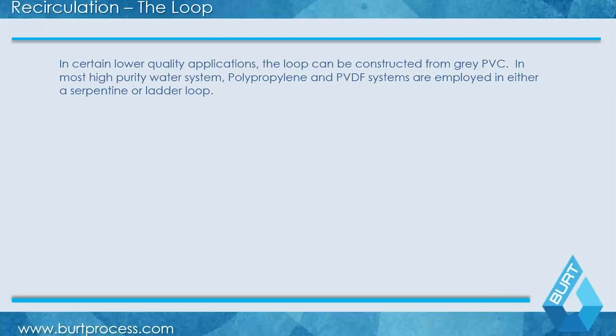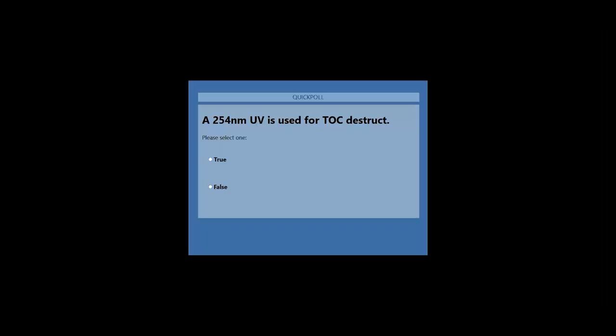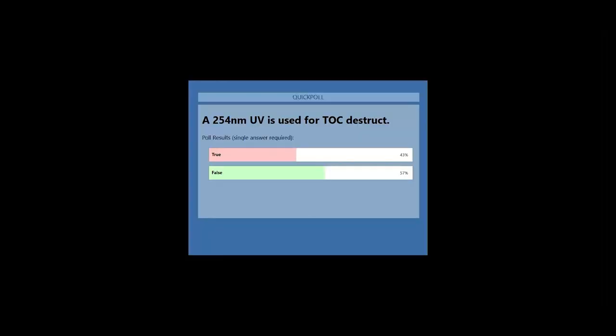Poll question: 254 nanometer UV is used for TOC destruction — true or false? The answer is false. 254 nanometer does not have the proper wavelength for TOC reduction. The two primary means of reducing TOC are your RO and your 185 nanometer UV light, which operates in the UV vacuum range to break down TOC.